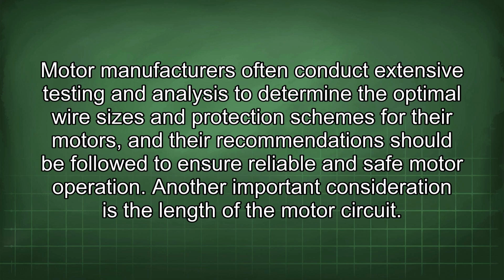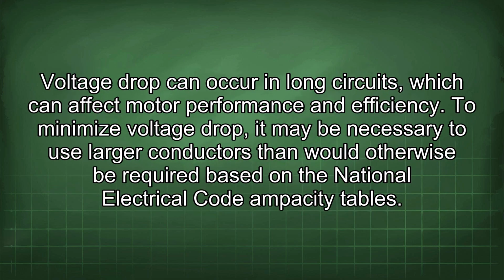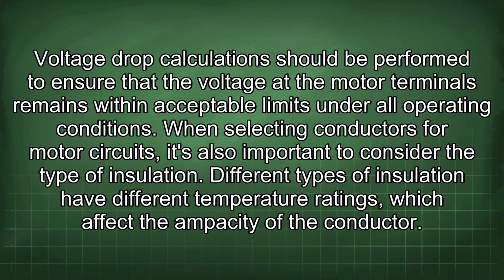Another important consideration is the length of the motor circuit. Voltage drop can occur in long circuits, which can affect motor performance and efficiency. To minimize voltage drop, it may be necessary to use larger conductors than would otherwise be required based on the National Electrical Code ampacity tables.